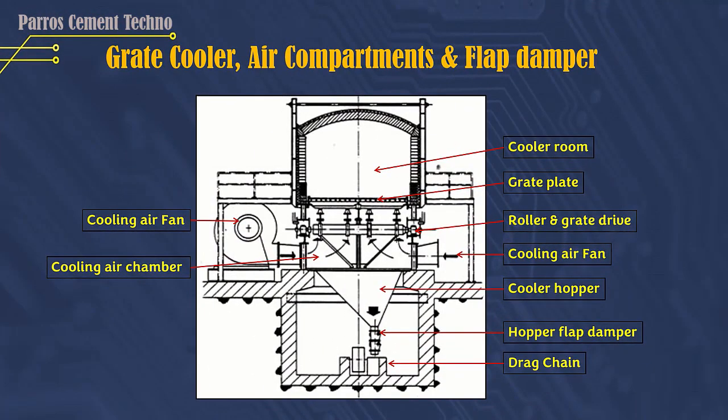This is a sample image of the grate cooler air compartment and damper flap. We can see in the picture there is a cooling room with grate plates installed, a roller driving the grate, a cooling air fan installed beside the cooling room, a cooling air chamber under the grate plate, and a hopper whose function is to collect clinker dust. There is also a damper flap to remove clinker dust by opening the damper flap, and a drag chain to transport the clinker dust material to the next transport means to the clinker silo.